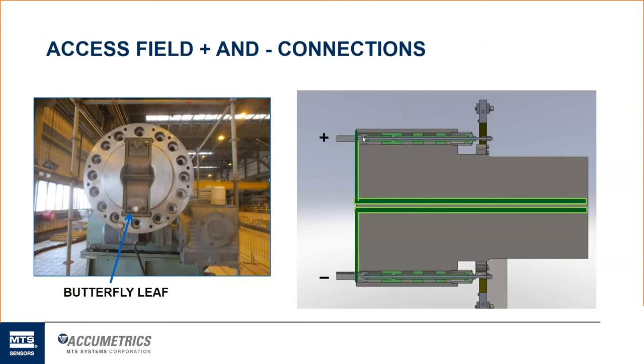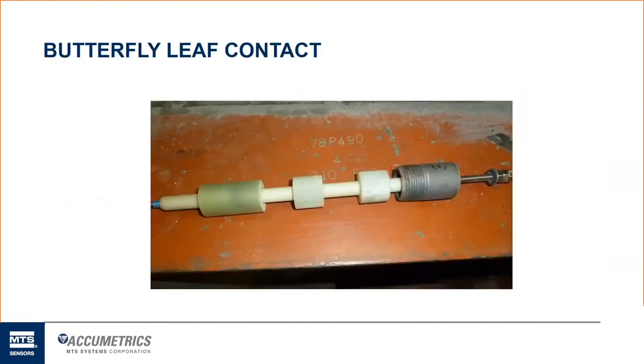And we just drill and tap a 1/4-20 stainless steel threaded rod right into one of those large hex head bolts. And we run our threaded rod right through that coupling flange bore directly into our rotor mounted transmitter. So that would be your plus and your minus field voltage connection. It's a very reliable way of getting access to that electrical connection, and is as least invasive as possible for the end users. They really don't have to modify any part of their machine except for that drilling and tapping of the two bolts where that contact is made. So that's an example of the butterfly leaf field voltage contact.